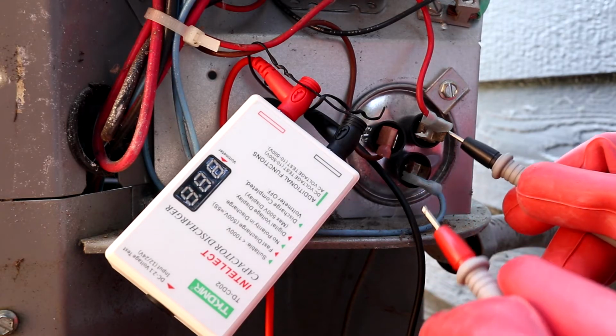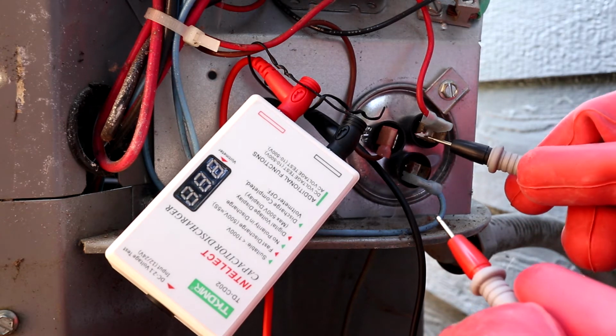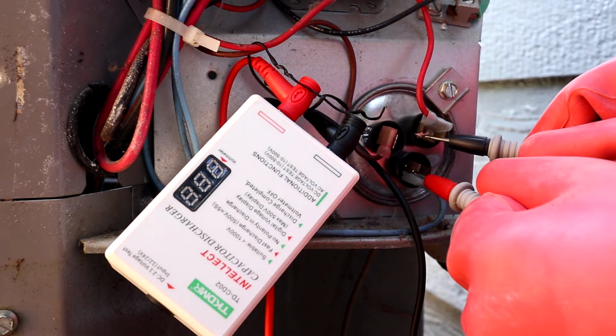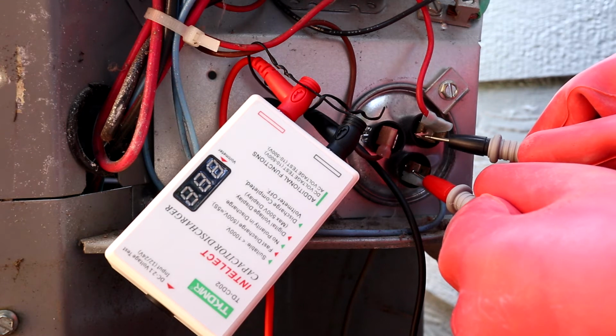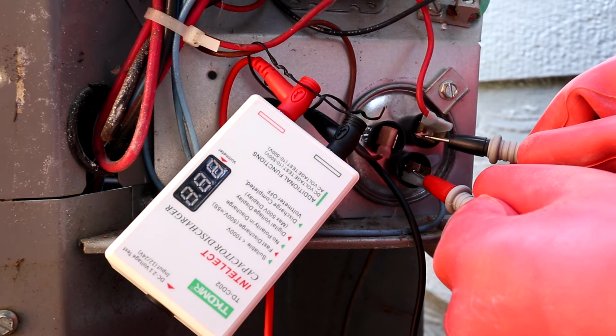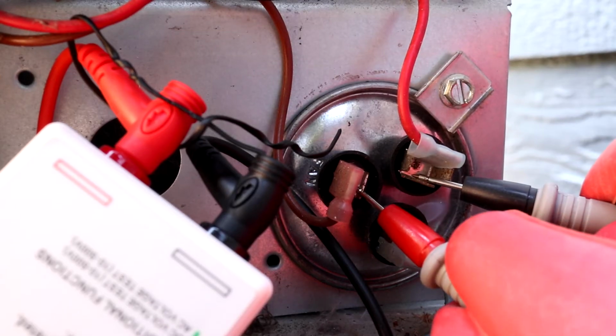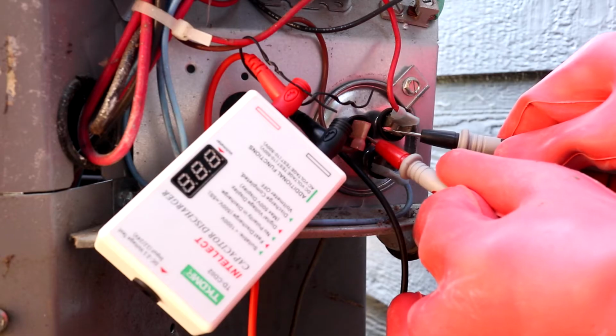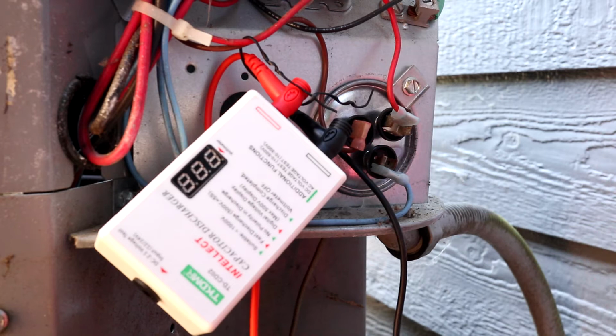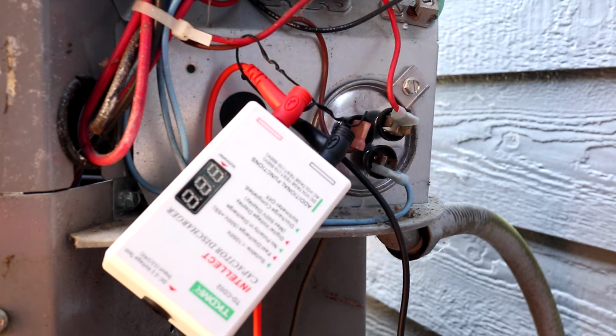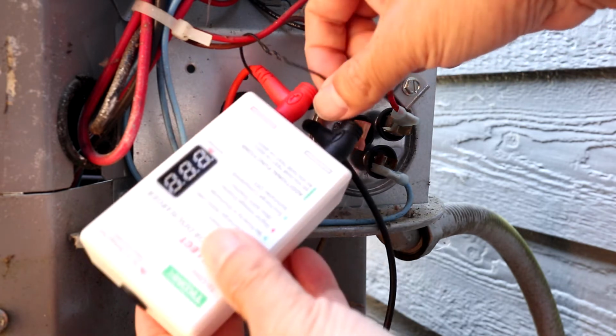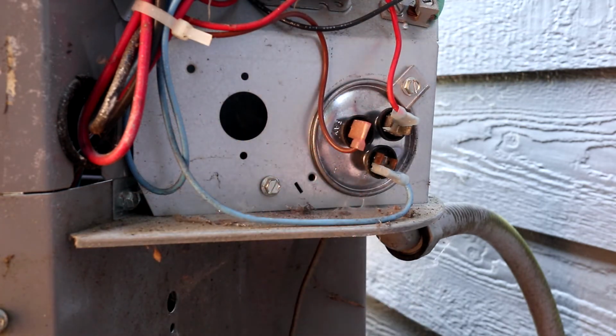First I'm going to discharge the capacitor by holding one of the probes of my discharge tool to the C terminal and the other on the HERM. Then I'll do this again by holding the probe on C and then the other on the fan terminal. These will be clearly labeled on the top of the capacitor. With this discharge tool, the display isn't lighting up because anything under 10 volts will not be shown on the meter, so I know this capacitor is discharged.